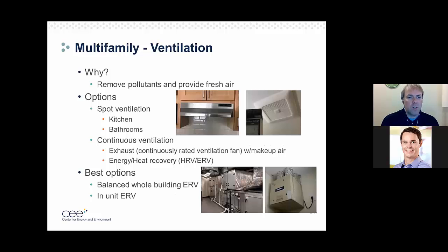Some options we have are spot ventilation - so we've got kitchen hoods like here, and bathroom fans like this. And we're looking at continuous ventilation as well. That's different - you want your spot ventilation to get rid of pollutants from the kitchen and bathroom, but you also want some kind of continuous fresh air brought into that apartment unit. With that, you can do an exhaust system where one of these fans is rated for continuous use, either a kitchen or bath fan, and then have some makeup air pulled in. It's more of a bare bones approach, or even better yet, you could do heat recovery with an ERV or an HRV.